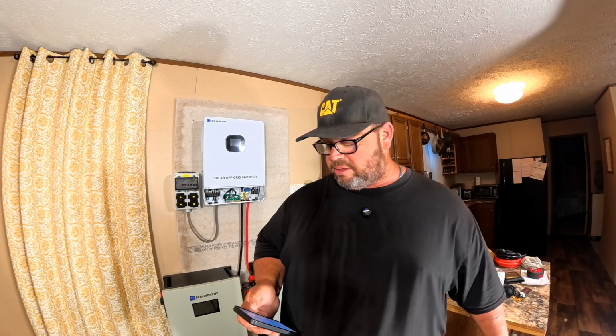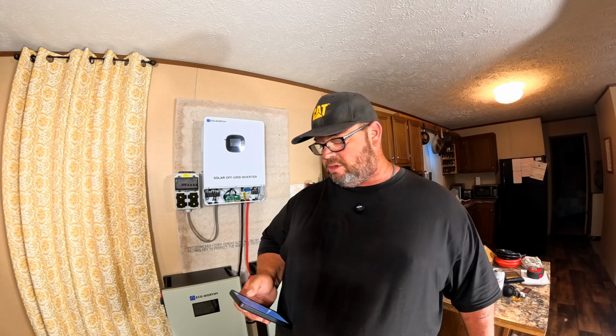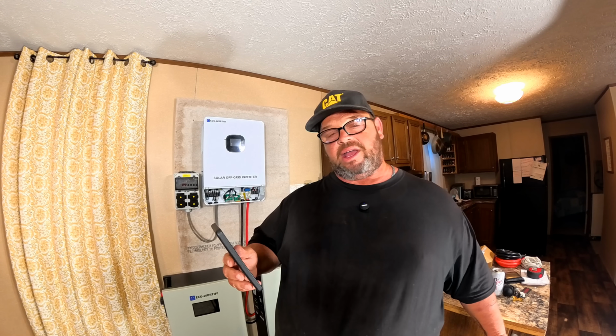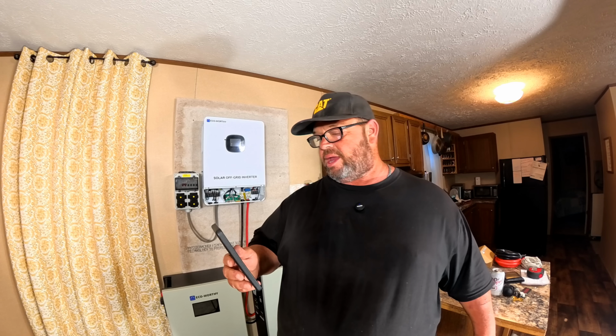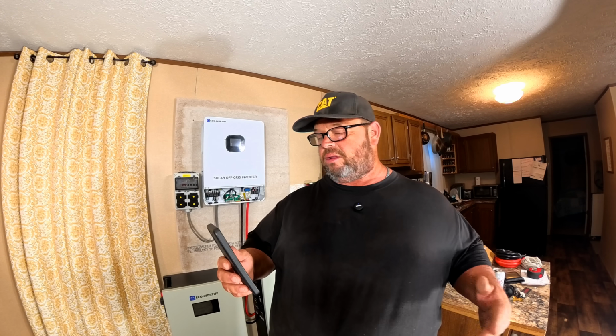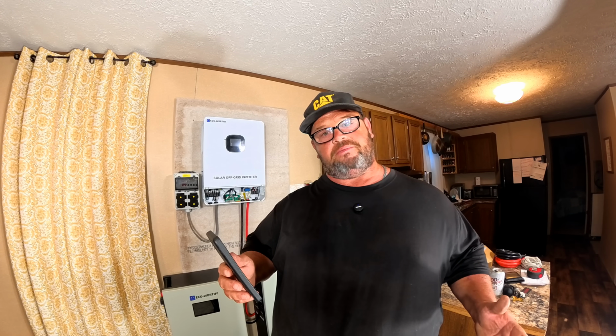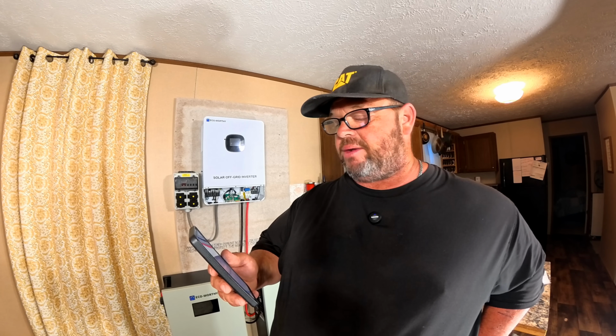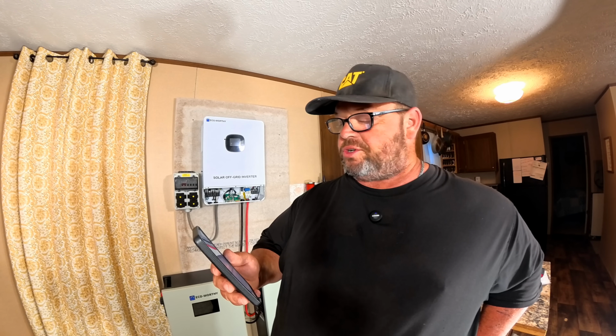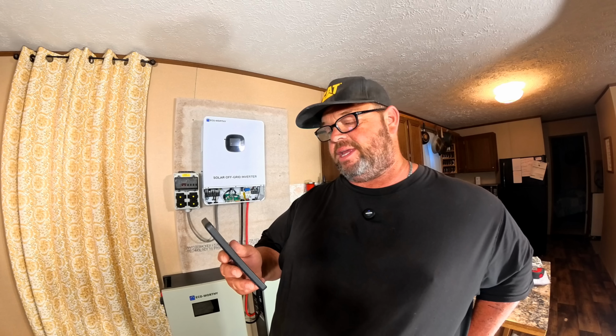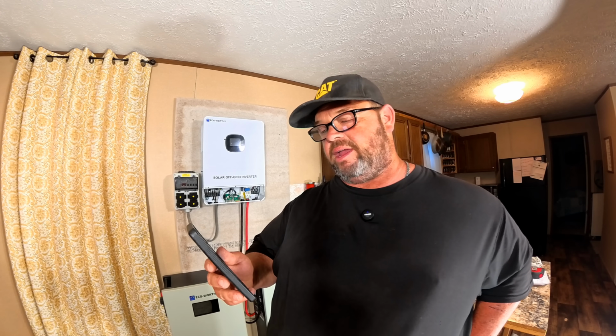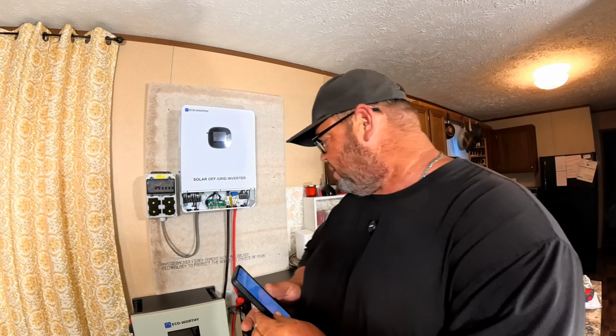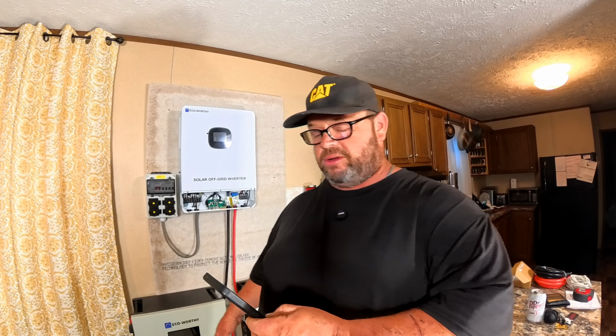Okay, we're going to be a little more clear for Google, make it a little easier. If I have a 16 kilowatt hour battery at 51.2 volts, how long will this run a 5,000 BTU air conditioner? It says if you have a 16 kilowatt hour battery at 51.2 volts, your battery has the capacity of 312.5 amp hours, which is a little off from here because this is 314 amp hour. It gives you a total of 16,000 watt hours.